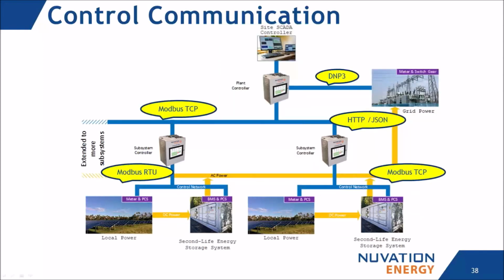At the top level, DNP3 is the suggested protocol for IEEE 1547. The SunSpec models, as we've been discussing before, work on industrial protocols, like Modbus TCP or RTU. Likewise, there's also support for JSON interactions via HTTP. So there's multiple protocols, and that's primarily what we're going to be talking about, the communication and the models going forward.